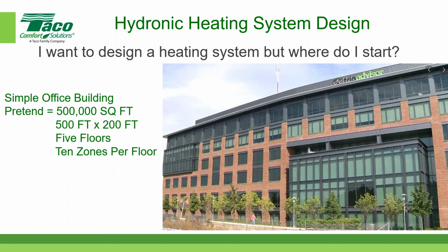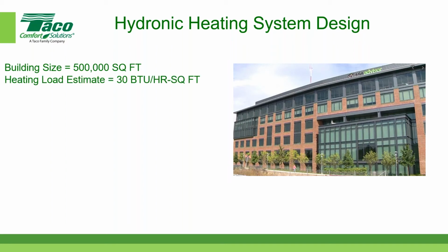The next thing I have to decide is, I have a separate presentation, which I'm not going to go into today, on how to design a central heating plant. But when it comes to designing a hydronic heating system, we do have to give some consideration to the fuel source. In our case, let's talk about the load first. The building size is 500,000 square feet, and I'm using an estimate of 30 BTUs per hour per square foot, which for the Northeast is a reasonable number. Depending on where you are in the country, the number would be higher in a colder climate or less in a warmer climate. So the heating load is estimated at 15 million BTUs per hour. That's simply 30 BTUs per hour per square foot times 500,000 square feet.